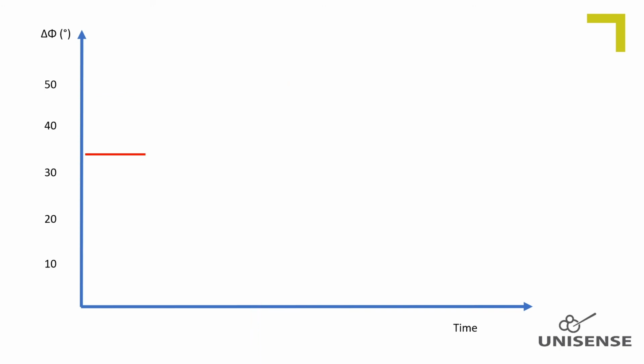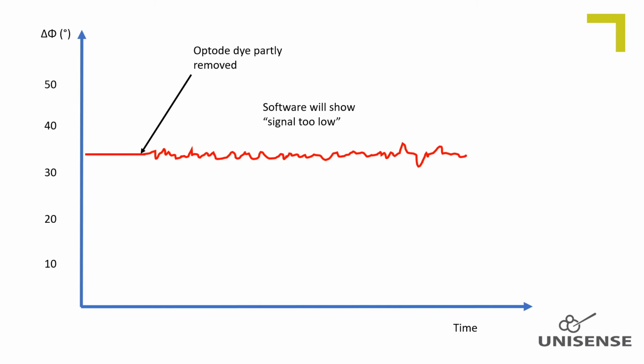When profiling in grinding matrices like sandy sediments or the like, the dye can be ripped off partly or completely. We recommend using amperometric Clark type sensors to profile such matrices. If the dye is partly ripped off, the software will show the signal too low indicator, and the noise level on both uncalibrated and calibrated signals will increase due to lack of data quality for the phase shift calculation. The less dye, the more noise.